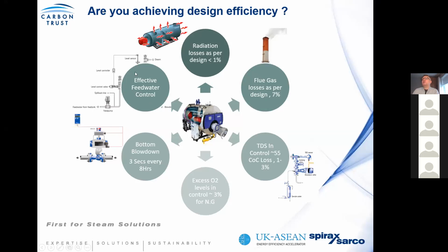We should also be looking at effective feed water control. Although a lot of companies say you should look at feed water modulation control, we're going to be introducing the concept of 2 or 3 element control as a means of counteracting the impacts of on-off process control, where you have standard level control and simple things like radiation losses. So in other words, it's a case of looking at all the different factors which contribute to a steam system and understanding where you sit in that process.